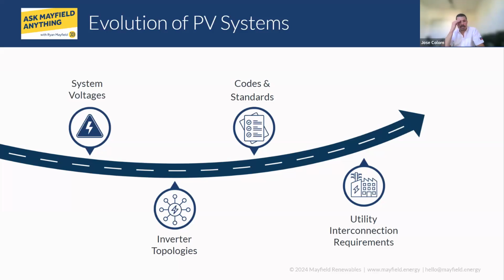So we see this question quite often, and I see that in the Q&A, we got a question which you already asked Joe about replacing SATCON units. We see that often, right? Mostly at the time, those were negative grounded systems, or how we're referring to them nowadays. What we do typically, at least our inverters require a floating array, right? So the way we work around this is we typically try to avoid restringing or having to tell the customer that they need to restring for their sites. So we potentially look into whether the solar company or the panels that are installed for that site would allow for any configuration of that array to become a floating array, right? If that's even possible, if it is something that was allowed after the site was implemented, then it could be an easy installation of our inverter at this point.